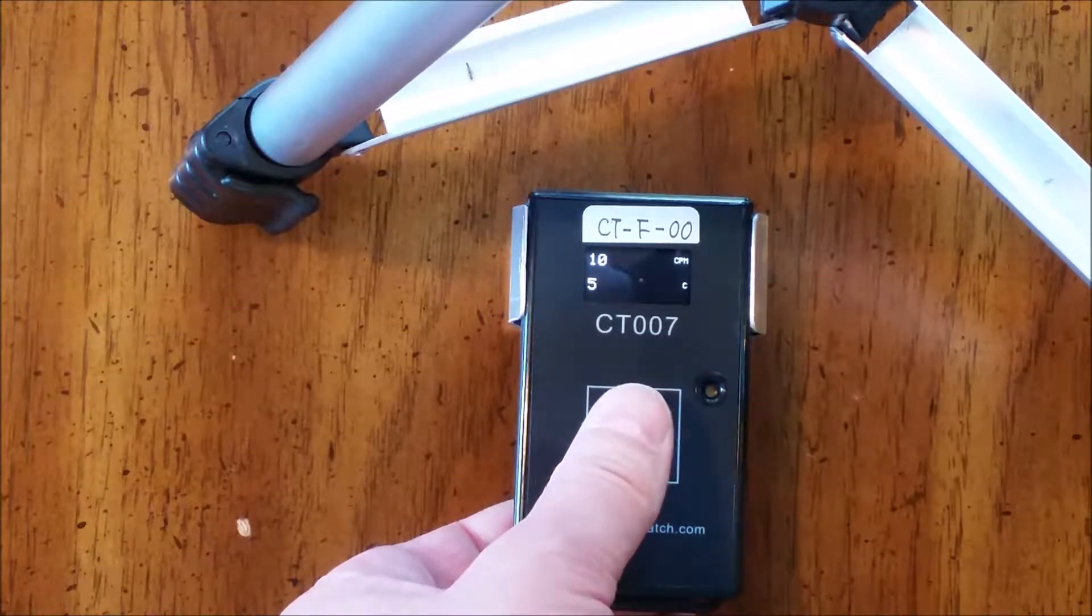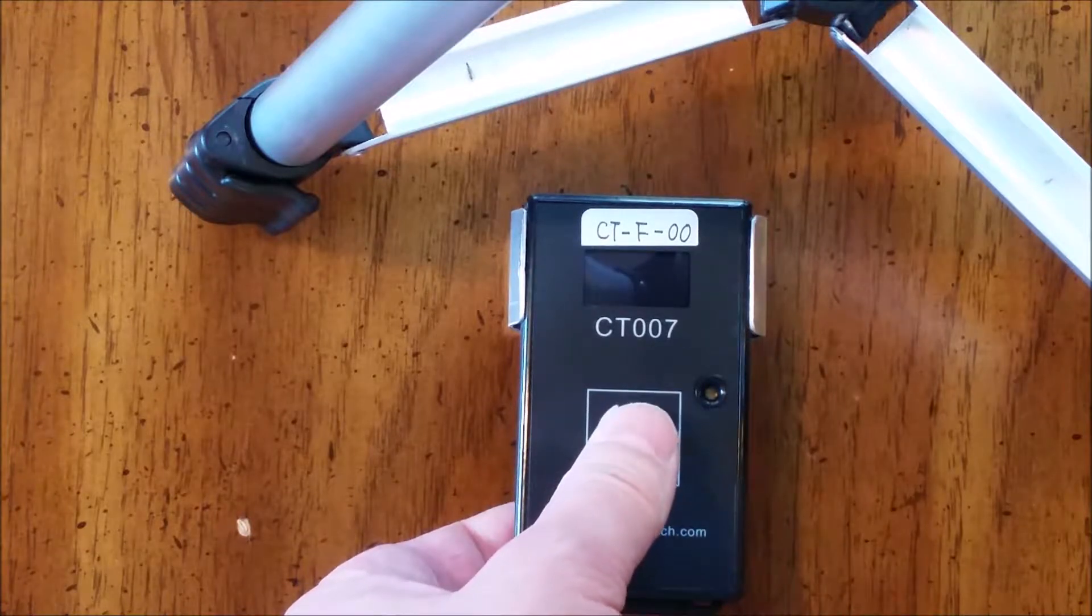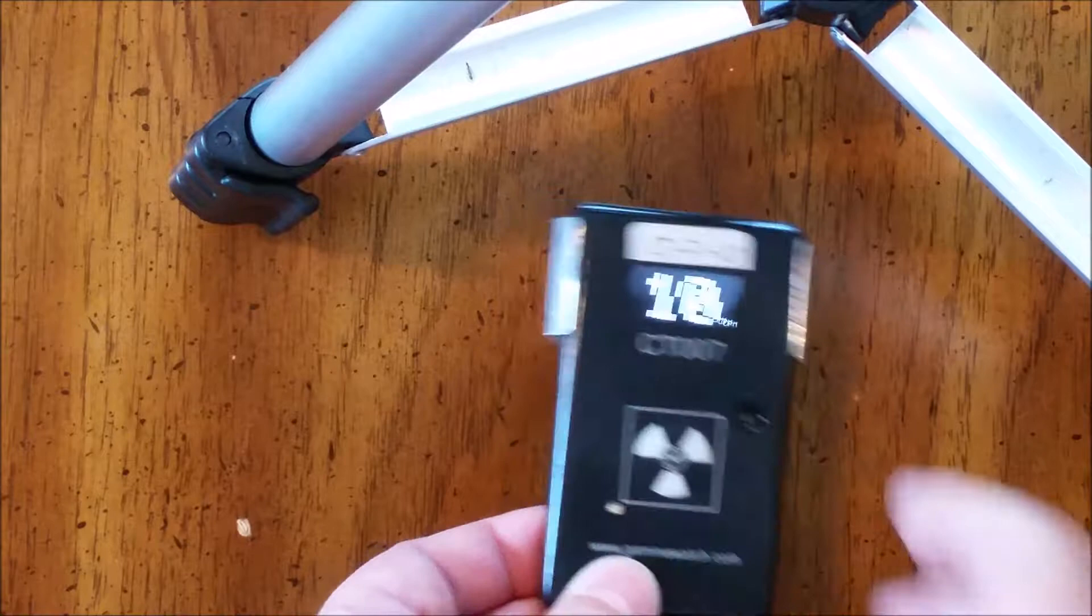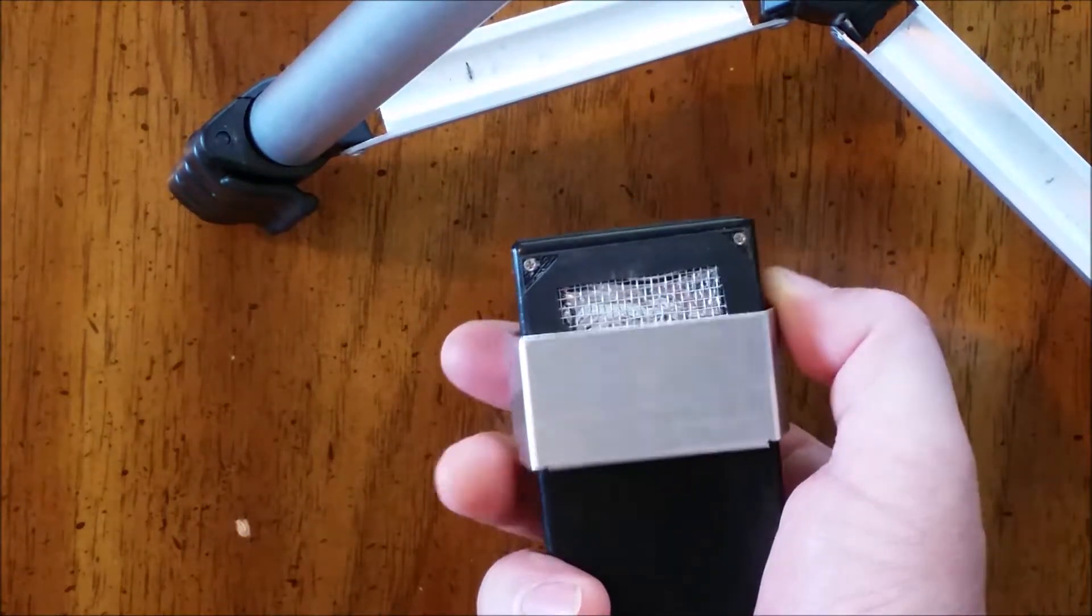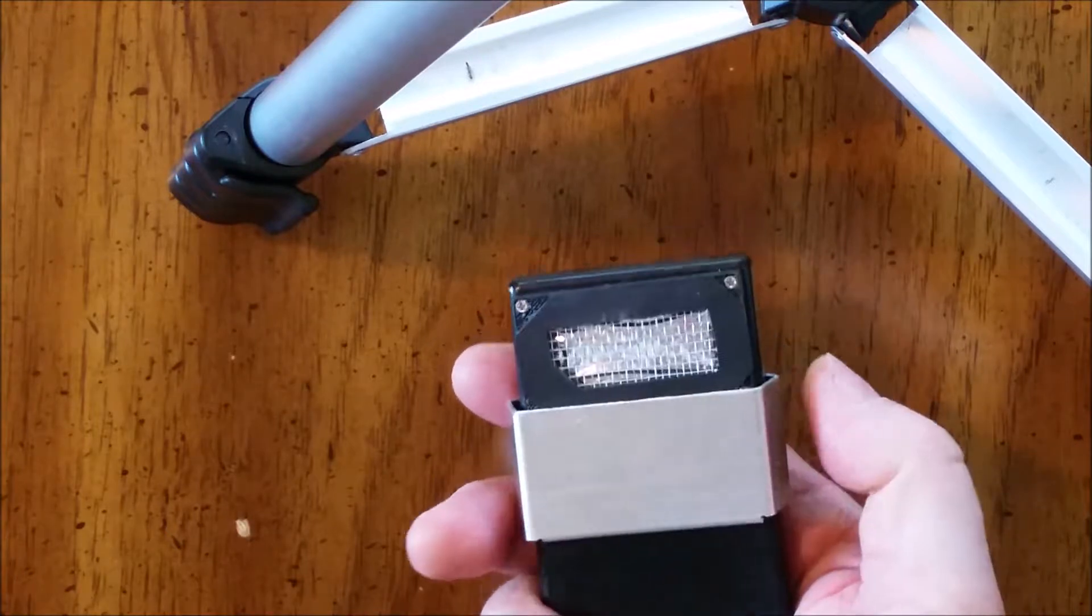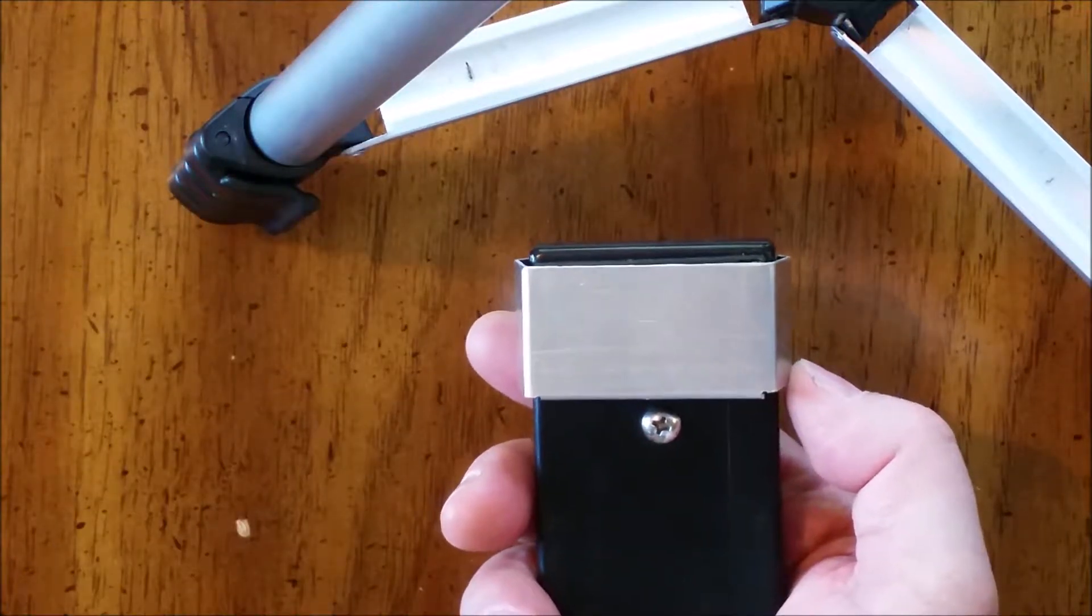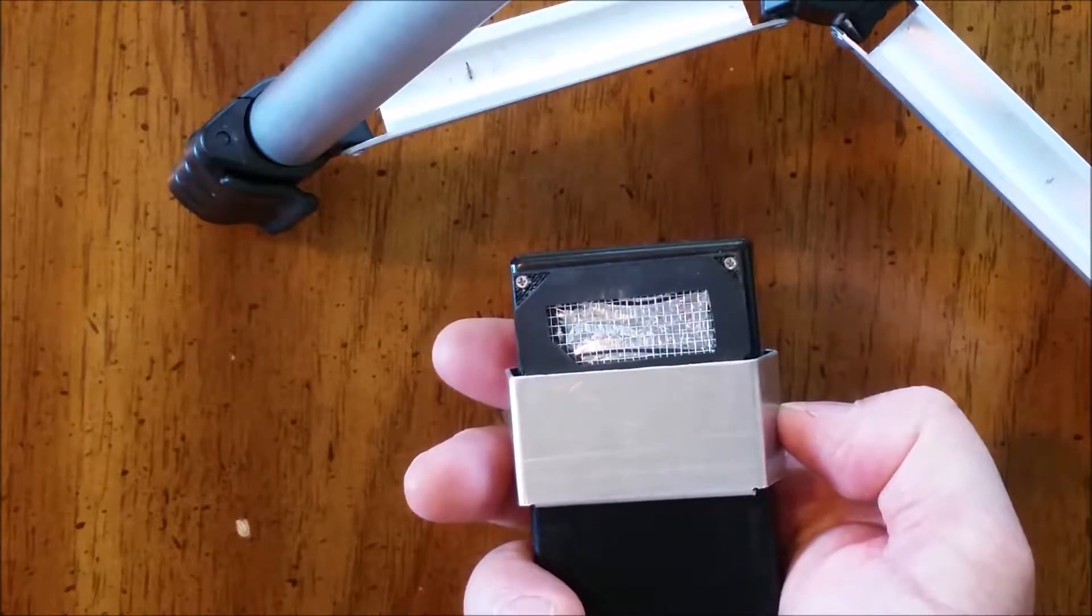Let's go back to our CPM display. The instrument has a sliding cover to protect the window. When that cover is closed, the instrument only sees gamma radiation. When it's open, we see alpha, beta, and gamma radiation.